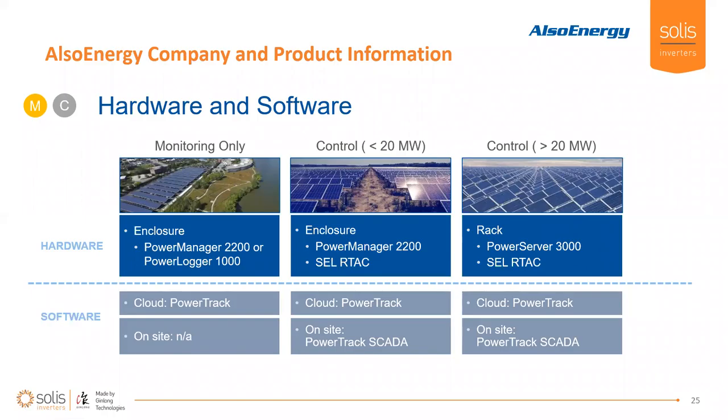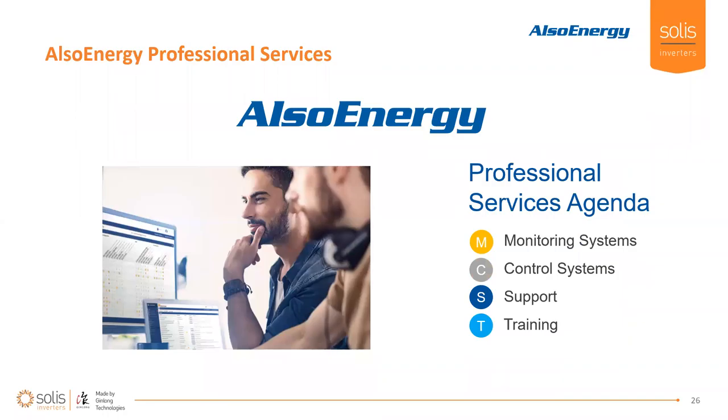On larger-scale applications above 20 megawatts, we'll typically opt to use a PowerServer 3000, which allows for an on-site historian, and then we'll use the SEL RTAC for power plant control. On these large-scale applications, we actually build a historian and real-time HMI on-site — we'll build it into those power servers, build that HMI on the Ignition platform, and execute our plant control via the SEL RTAC. This makes the plant completely portable — all data and functionality included within that SCADA system will transfer hands with that asset as the asset changes ownership.